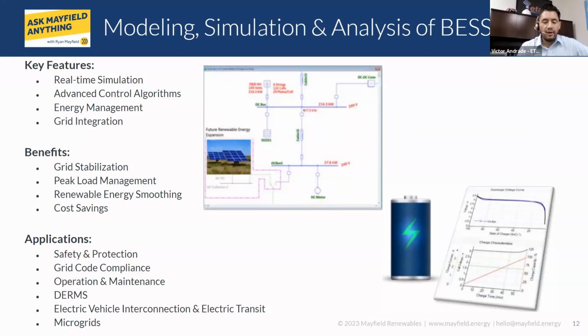So up to this point, we've only been talking about a PV farm. As systems become more decentralized, or you have, for example, the need to model storage, there is the ability to model battery energy and perform analysis like battery discharge. Many chemistries are supported, lithium ion, for example, lead acid. If you do industrial work, the battery side of a UPS is a lot of lead acid batteries. And yes, going back to the library question, there is a comprehensive library for everything from batteries to PV. The software allows you to connect the PV cells you select in parallel or series, smart inverters, protective devices, down to cables, from different manufacturers, and you basically plug and play like AutoCAD, connect them, and then just run your desired analysis.